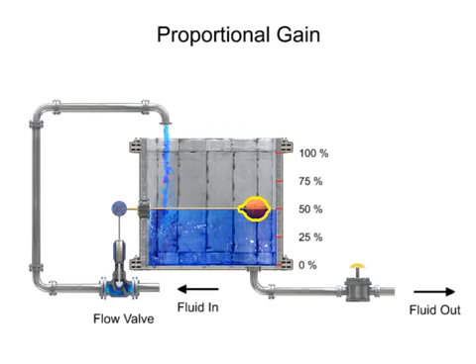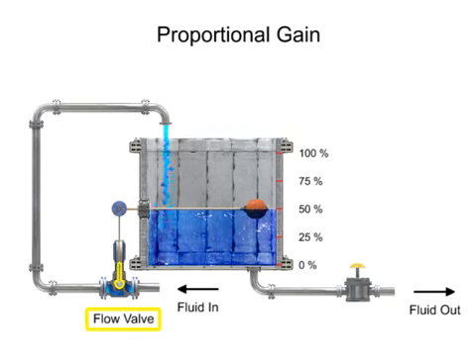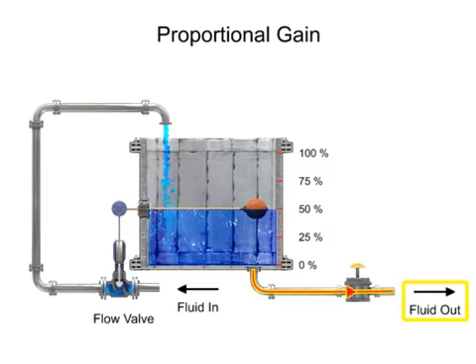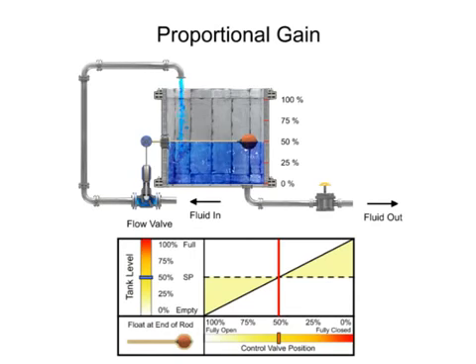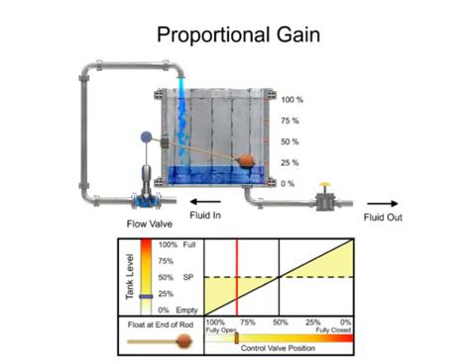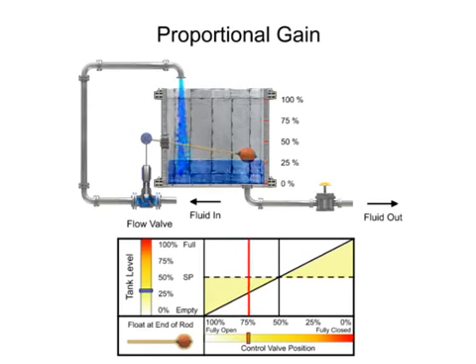The float mechanism is designed so that when the tank level is half-full, the flow valve is open to the position that causes the amount of fluid entering the tank to equal the amount leaving the tank. The float on the end of the rod is positioned to meet the minimum and maximum flow capability of the valve. The valve is actuated by the float to a fully open position when the tank level is low, and fully closed when the tank level is full.